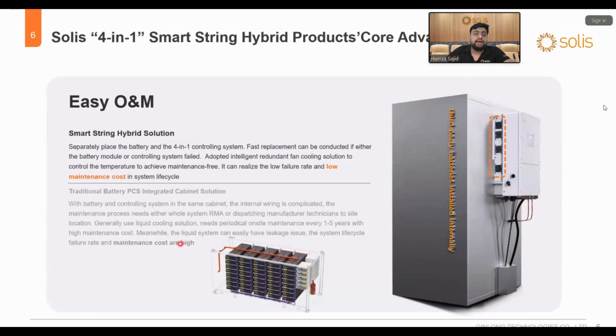Easy O&M. As the inverter is installed outside and it has a cooling system, like redundant fans available on the outside, you no need to open the boxes like in the traditional system, where you have to take out the modules for the O&M. And one more thing is, most of the cabinet solutions have a liquid cooling system, which can cause a leakage if you don't do maintenance.